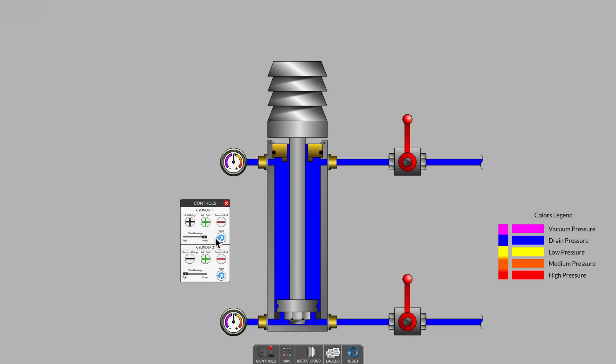If a cylinder does not have external leaks near the rod end, and it is drifting downward when it should be holding position, the common fault is usually found in the system valves that operate the cylinder.